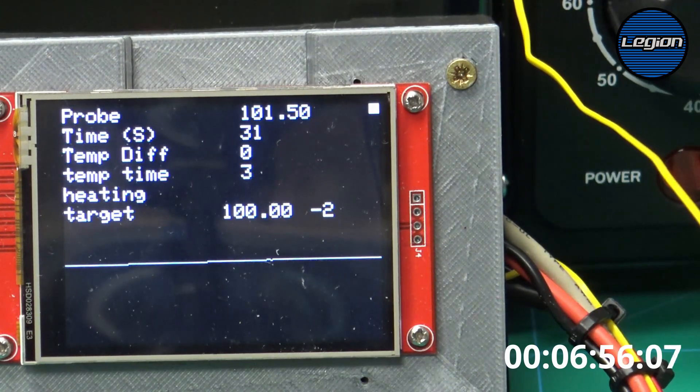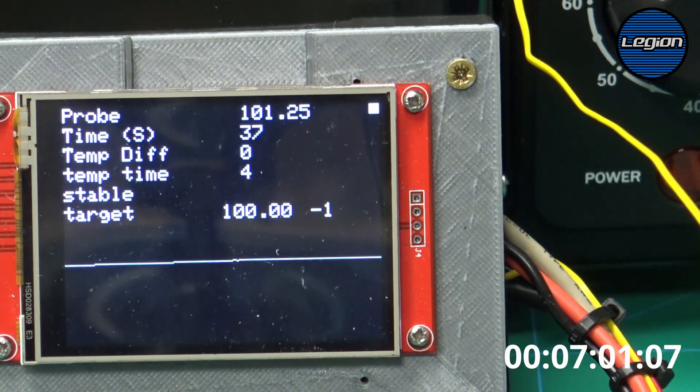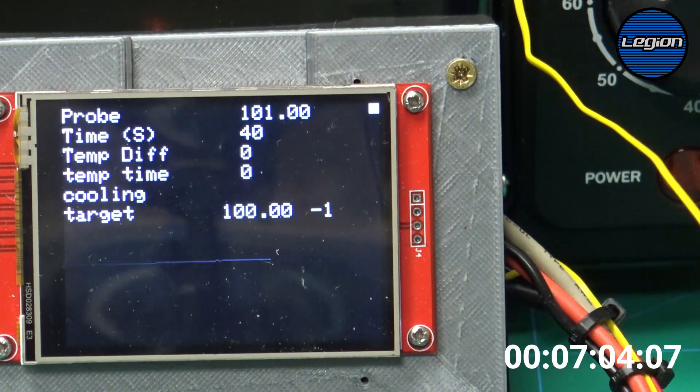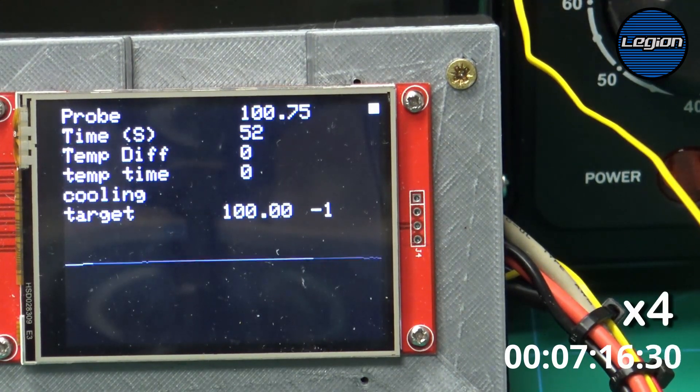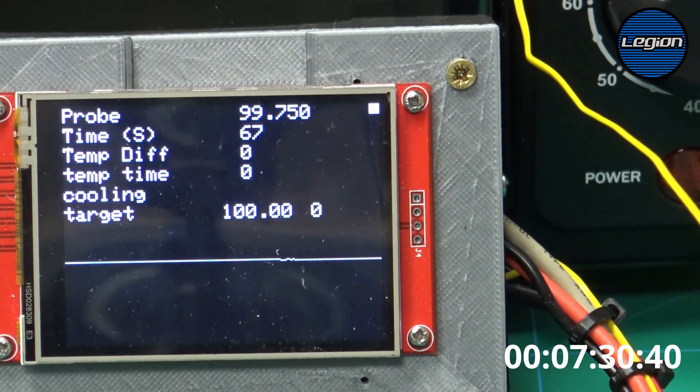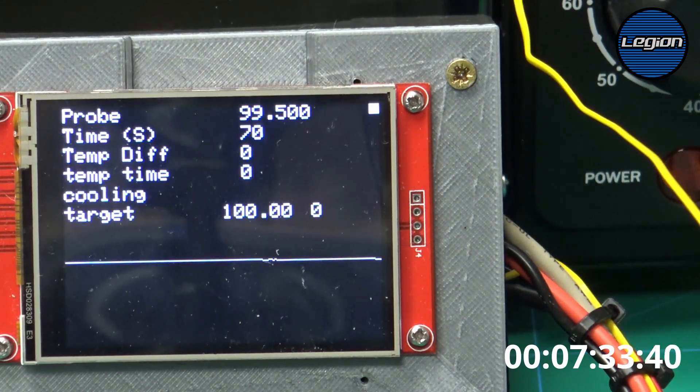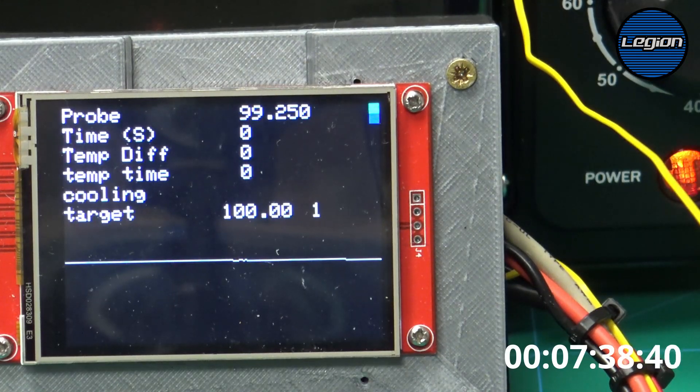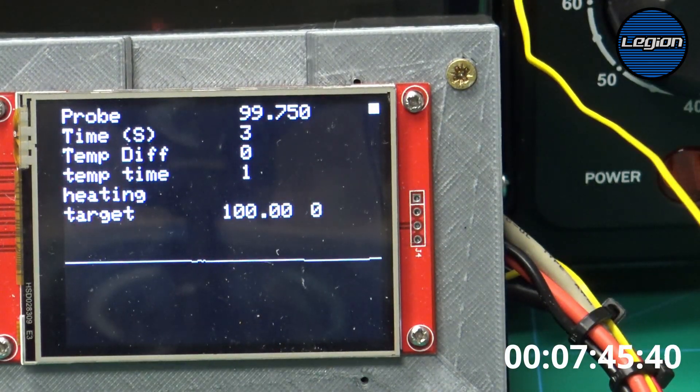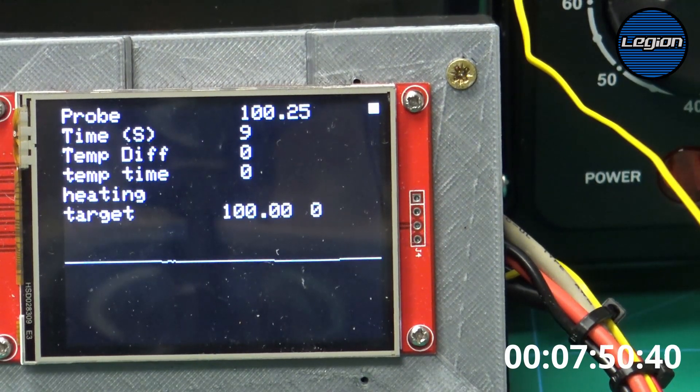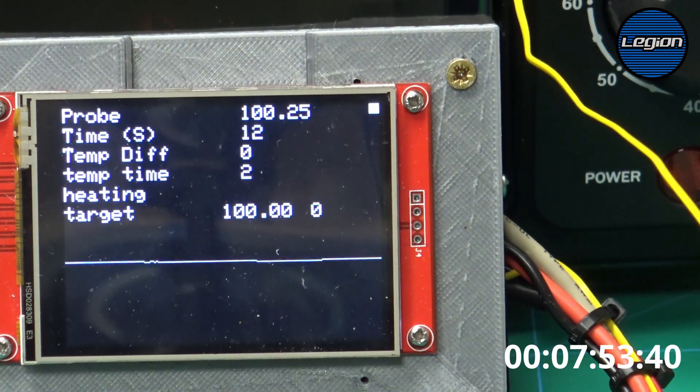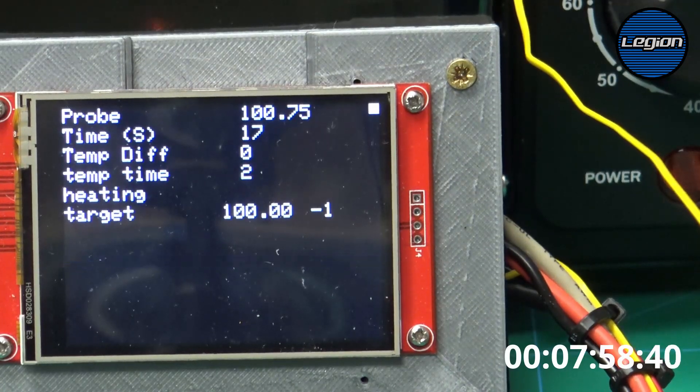So regardless of how long it's waiting, it sees that the temperature is dropping. I'm in the 1% range. I'm just going to blip it for half a second. So we're still in our target range. We're within 0% of our desired temperature. And it just dropped to 1%. And you can now see it thinks that it's cooling because it was dropping and it was blipping the temperature. It just put us back up to our target temperature. And it will just carry on like that.